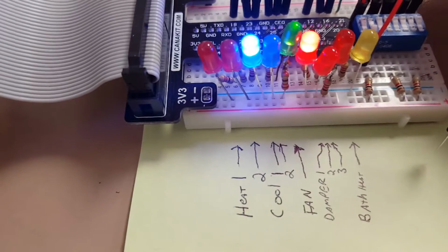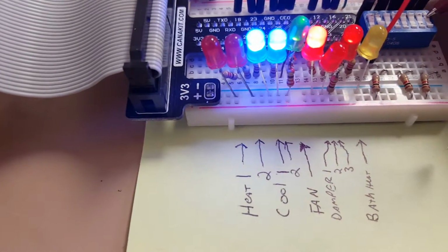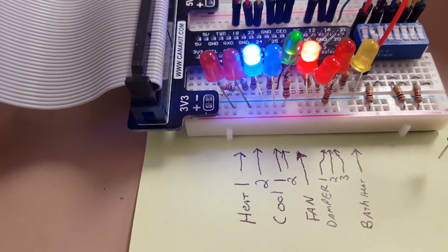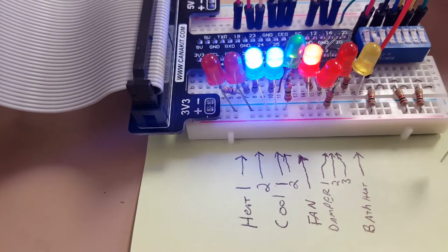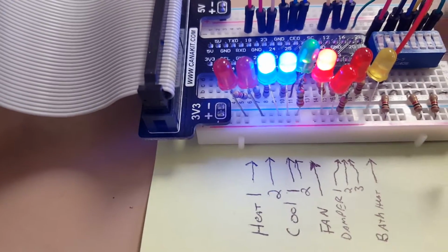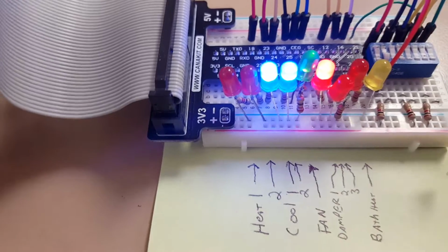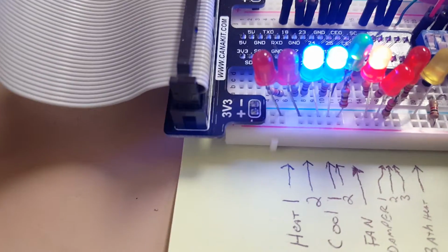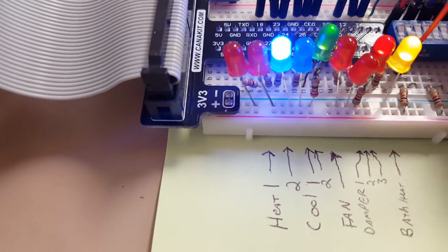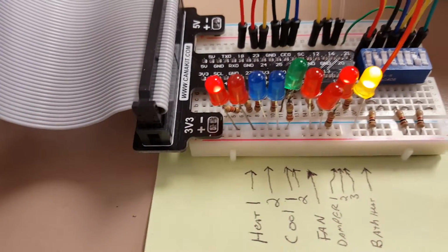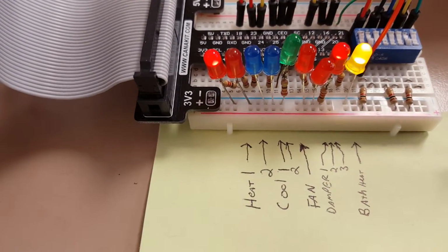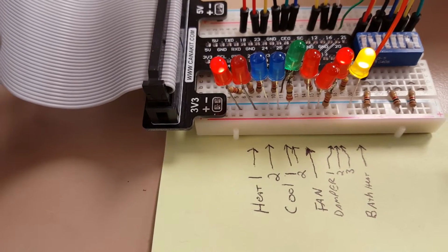Single stage, either another call for cooling will call for that other stage, or the time lapse will call for that other stage. And there it goes. One thing I built in is to make sure that the heating and cooling weren't running at the same time. If the upstairs was calling for cooling and the downstairs was calling for heating, I didn't want them running together. So I enabled that heating takes priority. And there you go. It's going to shut off cooling and shut off dampers to anything that isn't calling for heat.